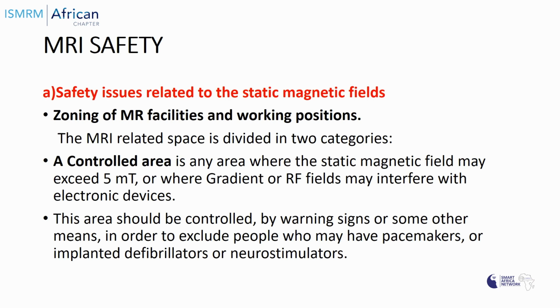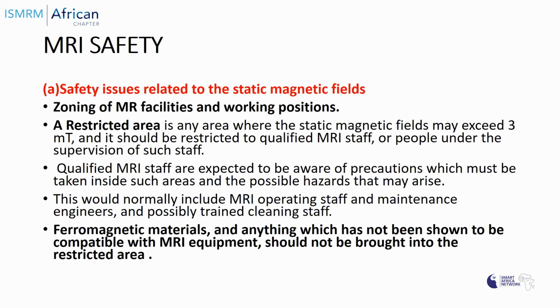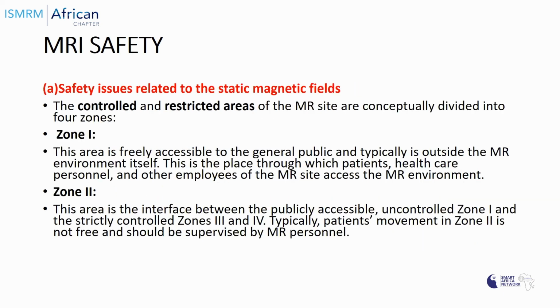who may have pacemakers or implanted defibrillators or neurostimulators. Zoning of MR facilities and working stations. We have a restricted area as well, any area where the static magnetic fields may exceed 3 mT, and it should be restricted to qualified MR staff or people under the supervision of such staff. Ferromagnetic materials and anything which has not been shown to be compatible with MR equipment should not be brought into the restricted area. The controlled and the restricted areas of the MR site are also divided into 4 zones.